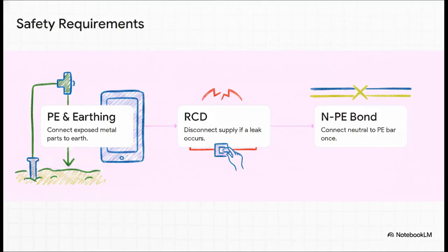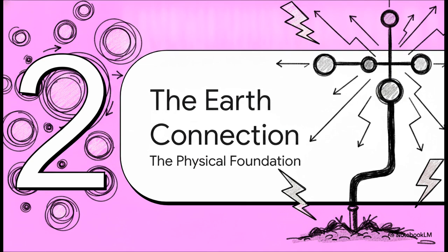Seriously, before you even think about connecting a single appliance to your system, you have to hit 3 major safety milestones. We're talking proper earthing, setting up an RCD, and making that NPE connection. Without these, your system literally cannot clear dangerous electrical faults safely. So let's build each one out. Moving on to part 2, foundation, the earth connection.